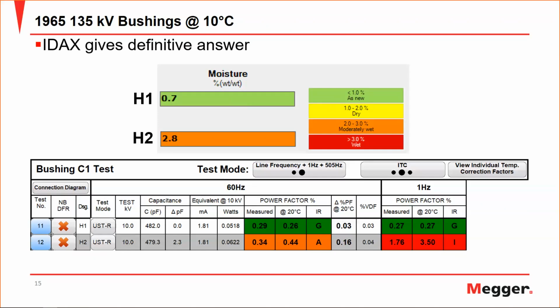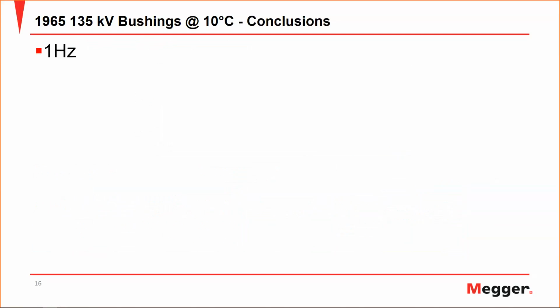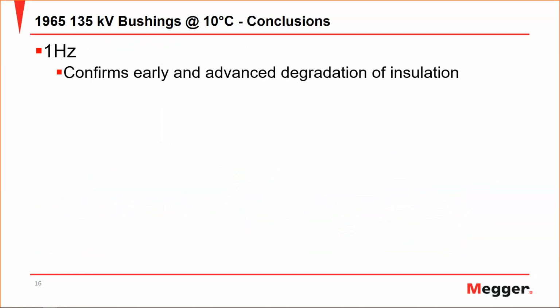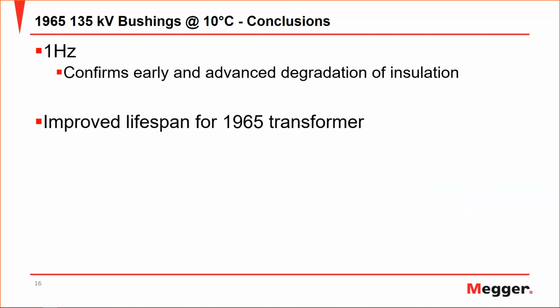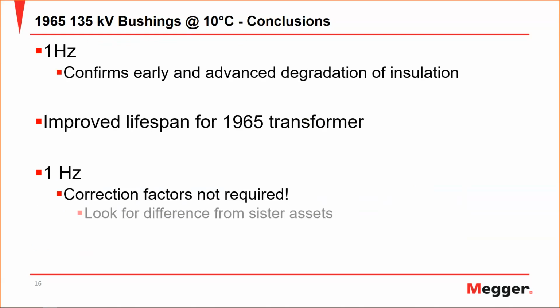We have less time to perform testing, and we need to see how to better focus our energy, and that 1 Hertz power factor testing gives you that capability. So again, looking at the 1 Hertz, this confirms early and advanced degradation of insulation. We have improved the lifespan of this 50-year-old transformer by identifying a problem bushing and giving the customer the ability to take action and rectify that. And with 1 Hertz, even if you don't use correction factors, you can just look for the difference from the sister assets.